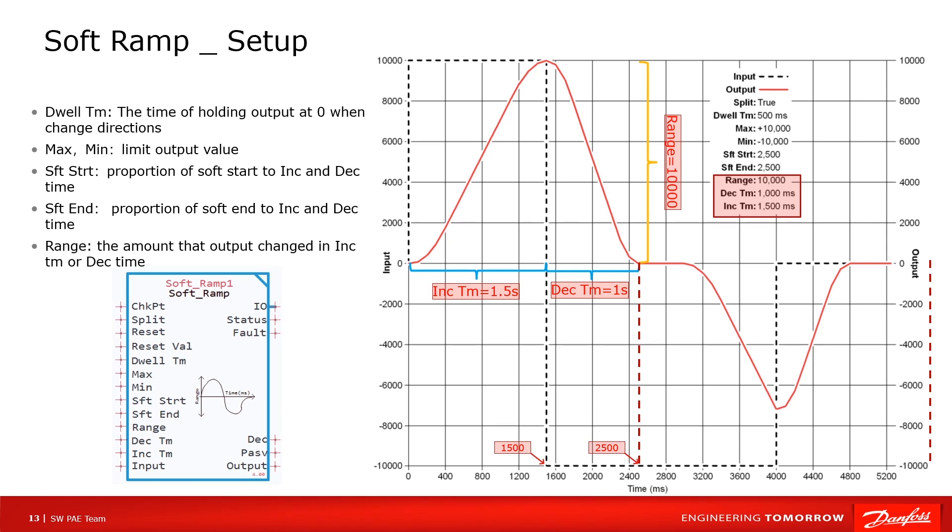For example, range is set to 10000. Increase time is set to 1500 milliseconds and decrease time is set to 1000 milliseconds. So it takes 1.5 seconds for output to increase from 0 to 10000 and 1 second for output to decrease from 10000 to 0.